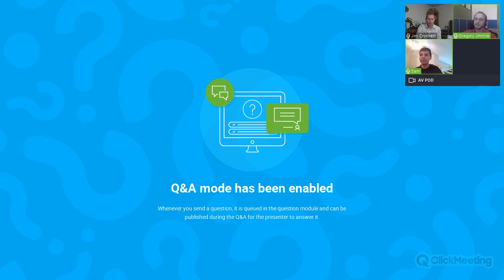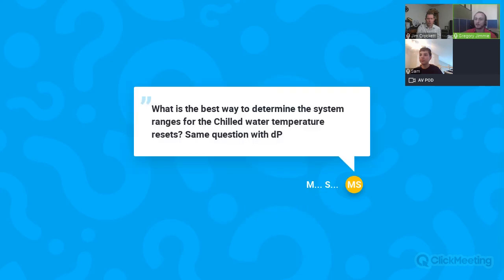There's a handful of cases in which maybe you used to be manufacturing and now you no longer do manufacturing in that facility, that will give you the room to maybe come off of that. But the bottom is a safe number to say this is where it was designed. You want to still allow the system to get to that design point, because it was engineered at some point or another that said this is where we need to get on the worst case scenario circumstances.